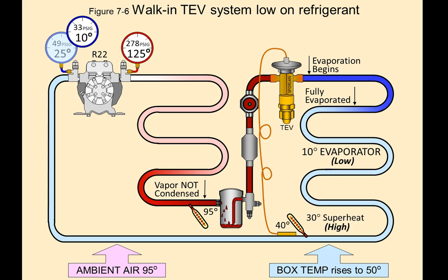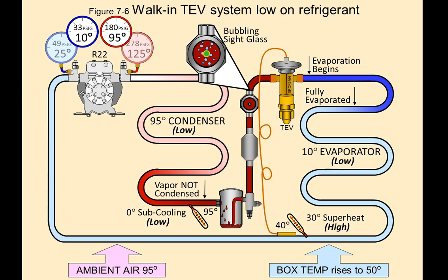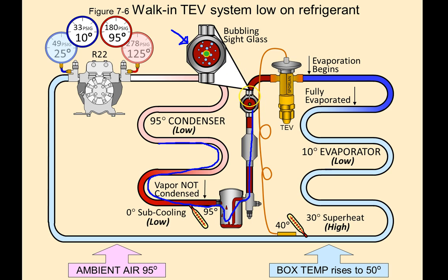On the condenser side, we have a lower pressure on the condensing side as well. Because there's not enough refrigerant, it pretty much blows through the condenser coil. Normally it would get backed up and begin sub-cooling, but because there's a lack of refrigerant, it doesn't get backed up. It blows through the condensing coil into the receiver, out of the receiver, and heads towards the TXV. You're going to see bubbles in the sight glass because it hasn't fully sub-cooled — it's still changing state from vapor to liquid.